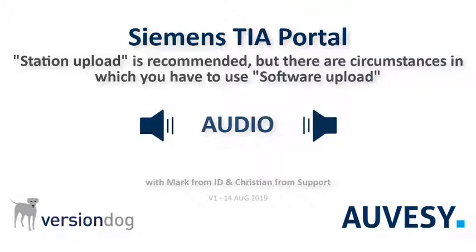And for those others, Software Upload is still a workable solution, isn't it? If they want a restorable backup — because we also have Checksum Compare only if you just want to monitor PLCs for changes. But what about people with S7-1500s and versions of TIA Portal earlier than 15.1? Siemens theoretically offers to migrate the programmed data to TIA Portal 15.1, but sometimes customers do not have this possibility, so they still have the option with Software Upload.